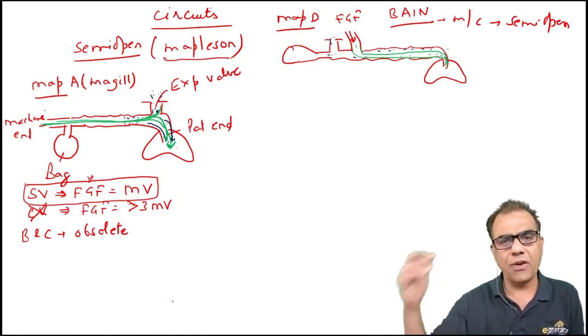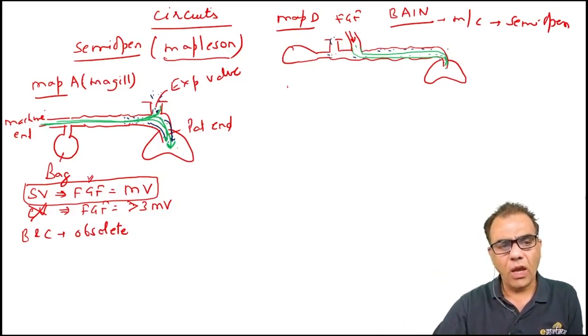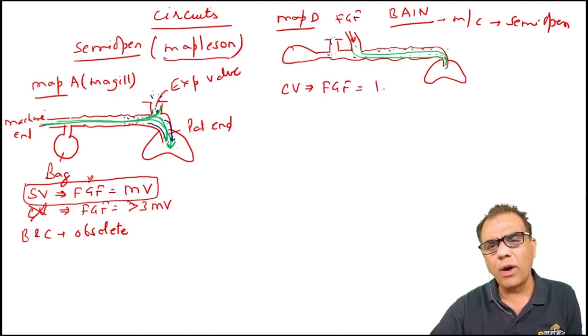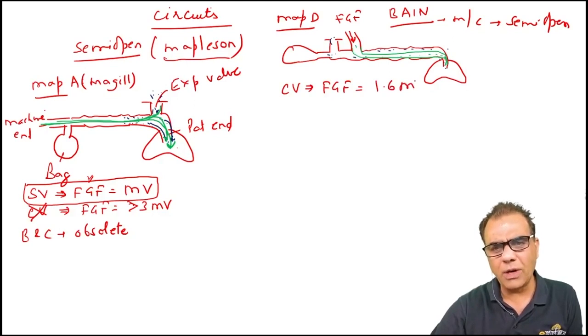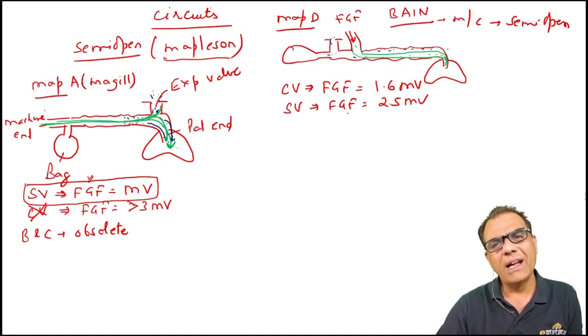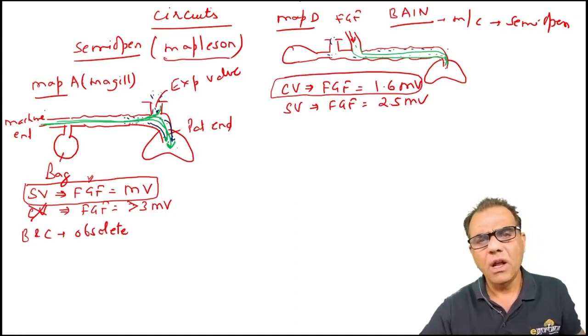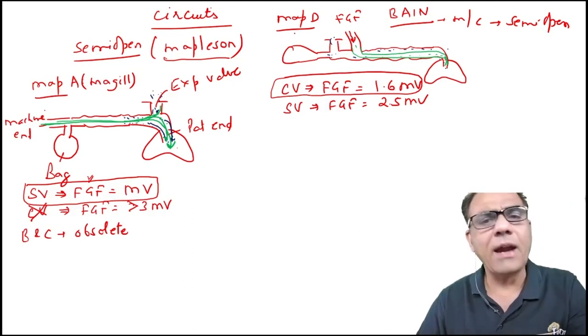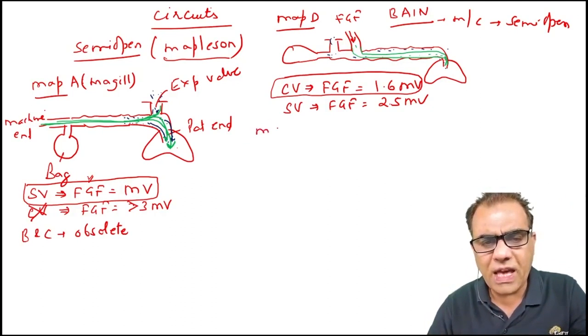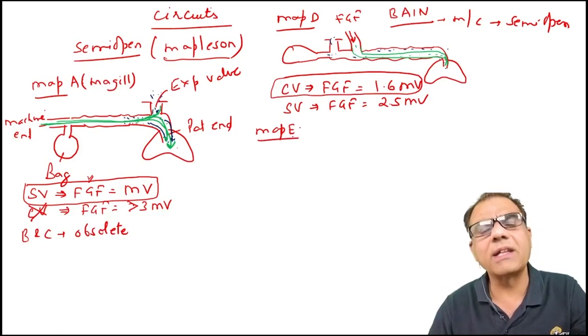Semi-open circuit. And fresh gas flow recommendations for Bain's, if you are using it for controlled ventilation, fresh gas flow should be around 1.5 to 2 times, so on average you can say 1.6 times the minute volume. If you use it for spontaneous ventilation, fresh gas flow requirement is high, and that is 2.5 times the minute volume, which is high. So it is not preferred for spontaneous ventilation, or in other words, you can say it is a circuit of choice for controlled ventilation. So until here these are adult circuits, while Mapleson E and Mapleson F are pediatric circuits.